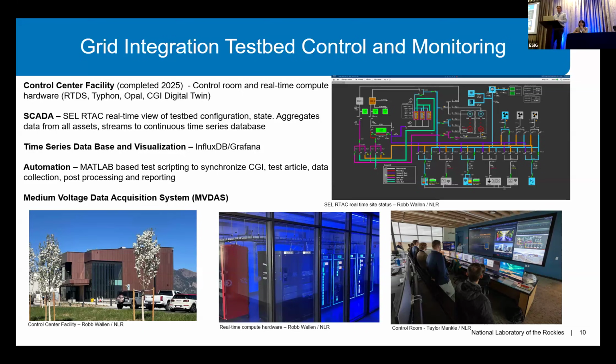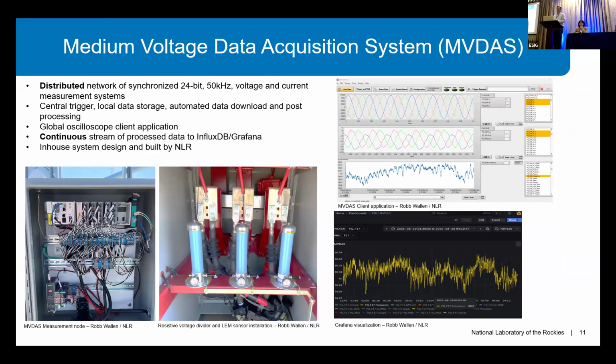For data acquisition, we have PMUs and obviously all the SEL equipment. We also have our medium voltage data acquisition system. This is a system built in-house by NREL. It's a distributed network of GPS synchronized 24-bit 50 kilohertz voltage and current measurements. We have about 40 of these nodes running all across our site, and we can pick which nodes we want and trigger them, and then they'll store locally, and then we can pull the data back with our scripting and then realign it and post-process it.